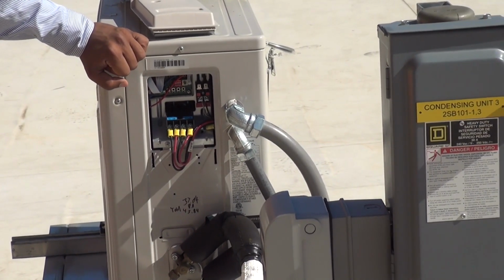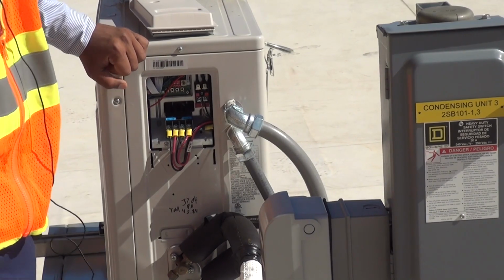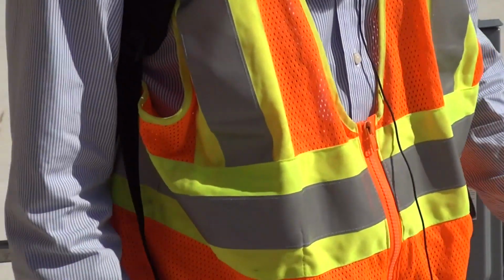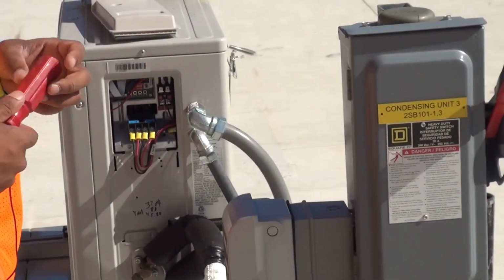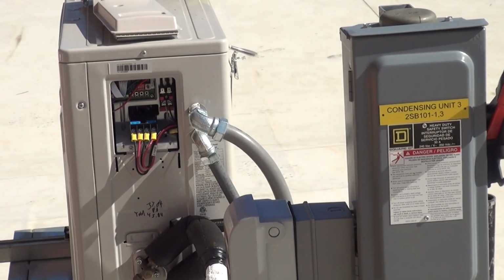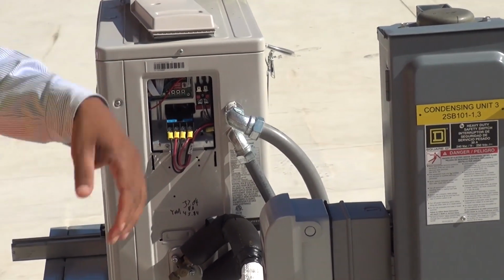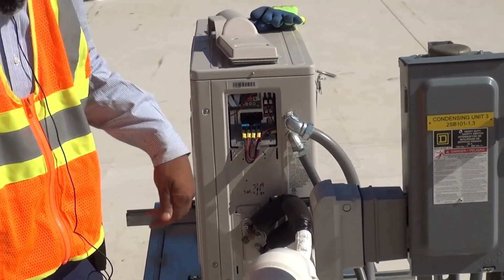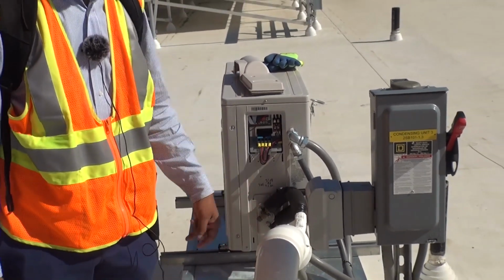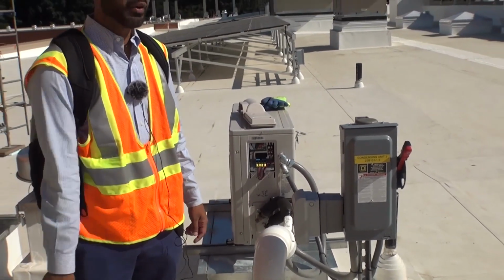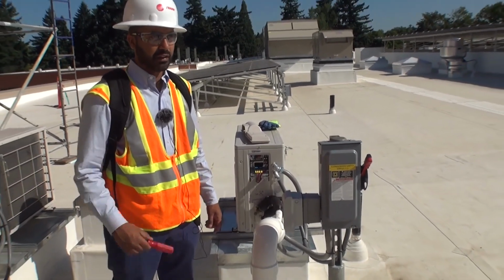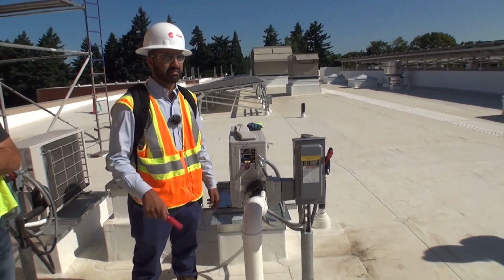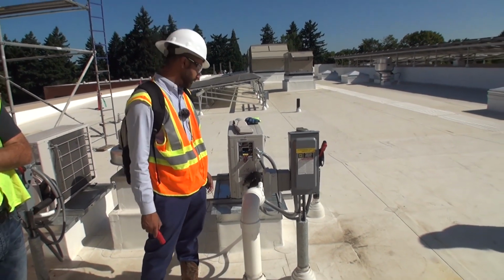So the evaporator's iced up? If the evaporator's iced up - yeah, evaporator icing up is fairly uncommon with ductless units. With the modulation that they have, they won't ever allow the temperature of the coil to go low enough. Now it will happen if you have perhaps a leak and low refrigerant, and that's going to ice up the refrigerant coil.